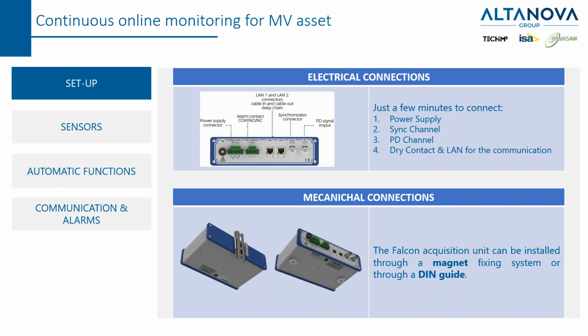Now, a few details about the unit and its setup. The unit has the power supply connectors, the dry contact on the front panel, and 2 LAN ports for the communication. That means that you can put many Falcons in a daisy chain layout, or use one single port to connect your laptop to immediately check the status of the asset. There is a channel for the synchronization, and one single channel for the partial discharge detection, and this has to be connected to the sensor. Okay, the typical installation of the Falcon unit is with the magnets, but it can also be installed using the DIN rail.